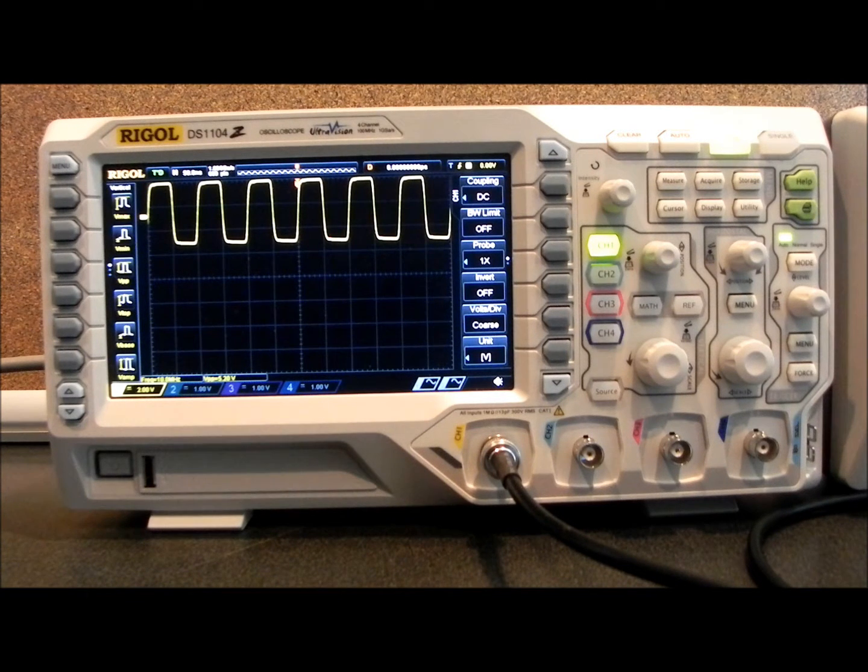This new firmware revision, 00.04.03 SP1, which is available through an authorized Rigol distribution or support center near you, has a feature that enables deep memory on the FFT. I'd like to show you exactly what that does on the display of the oscilloscope.